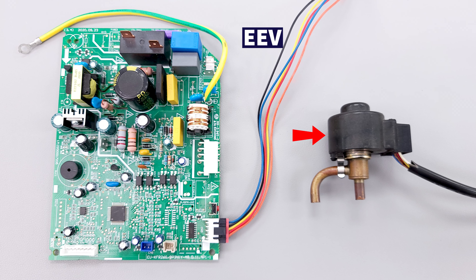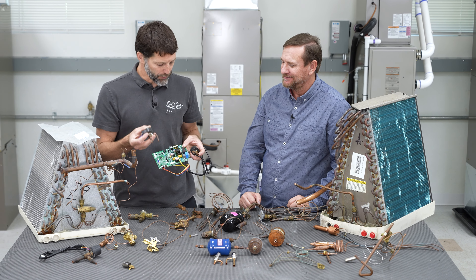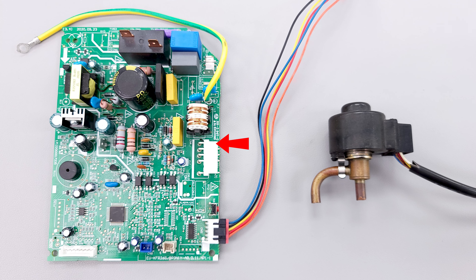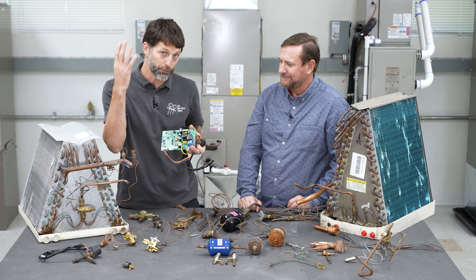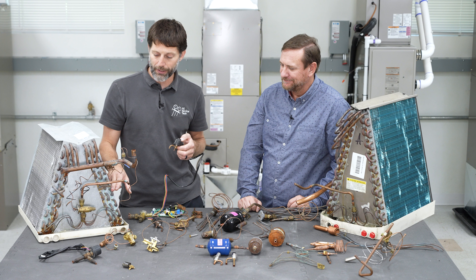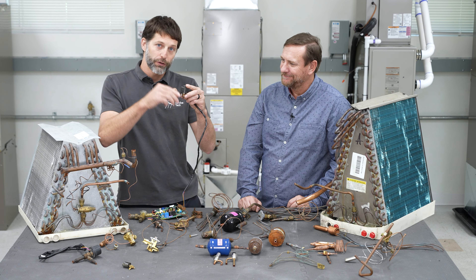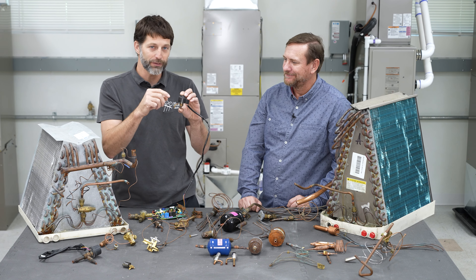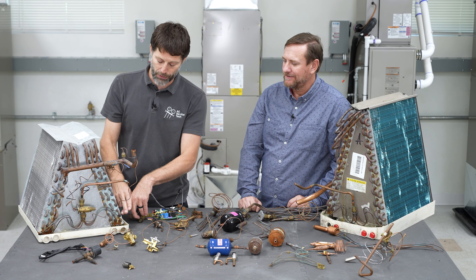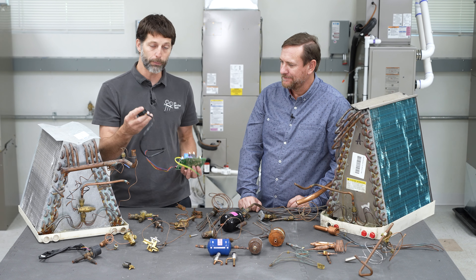As much as I like mechanical thermostatic expansion valves, now we have electronic expansion valves that do the same thing — opening and closing to control the amount of refrigerant inside the evaporator coil. This is a circuit board off of a mini split; it monitors the coil temperature and air temperature to open or close the pathway. On a ducted air conditioning system, it might measure the coil temperature and suction line temperature for the circuit board to make decisions. The object is that the EEV makes very minute changes to the internal pathway to maintain an effective superheat and therefore an effective amount of phase-changing refrigerant in the coil. It operates on 12-volt pulses heading to it to open or close the pathway.